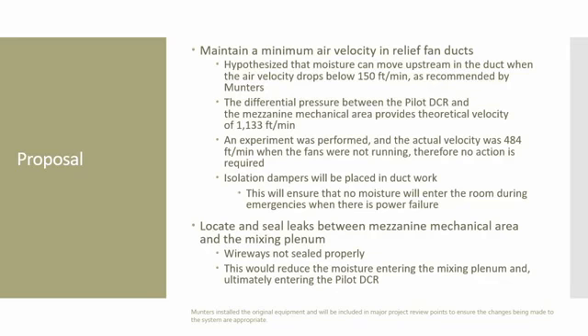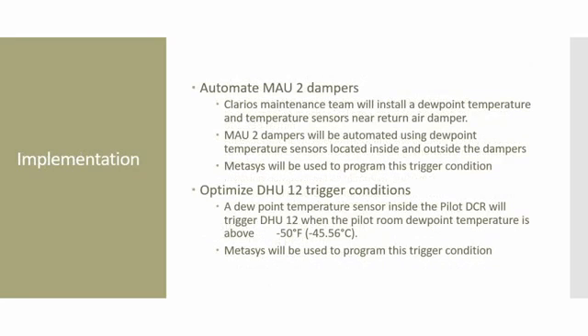For the implementation phase of the project, the Clarios maintenance team will install dew point temperature and temperature sensors near the return air damper. By using the sensors, the dampers will be automated with Metasys programming completed by a certified Metasys programming company. The dew point sensor within the pilot DCR will be triggered proactively at a dew point temperature that is above -50 degrees Fahrenheit. This will also be programmed into Metasys.